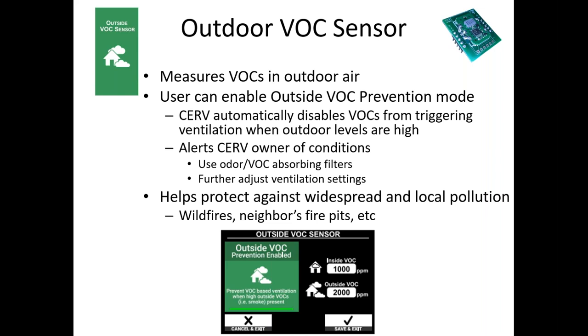Wildfires especially, as things have gotten really bad, you may want to disable all ventilation from occurring, and you yourself manually trigger ventilation for a short period of time when you know it's not smoky outside. I know some of our customers out west, things have just been so bad that you really want the system running in recirculation mode inside, and there are periods of time when you don't want any ventilation to occur.